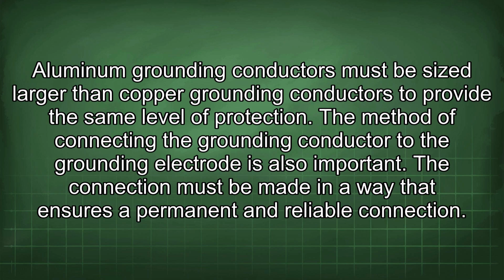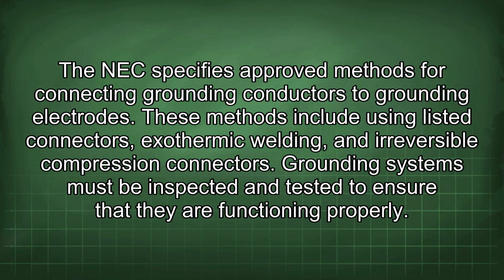The method of connecting the grounding conductor to the grounding electrode is also important. The connection must be made in a way that ensures a permanent and reliable connection. The NEC specifies approved methods for connecting grounding conductors to grounding electrodes. These methods include using listed connectors, exothermic welding, and irreversible compression connectors. Grounding systems must be inspected and tested to ensure that they are functioning properly.